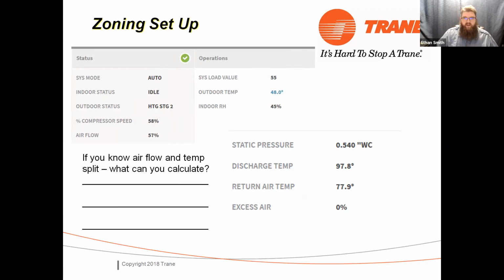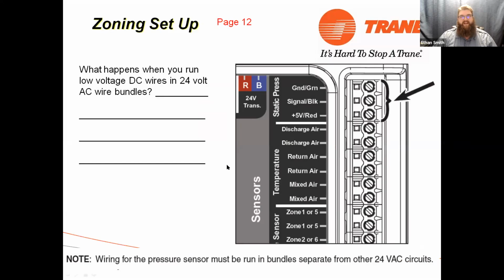I have more than once pulled up zoning systems to help guys with them and seen that discharge air temperature read the ambient in the mechanical room. So we can tell if you take the discharge air temperature sensor out of the ductwork to keep it from tripping on the discharge air limit. Okay.